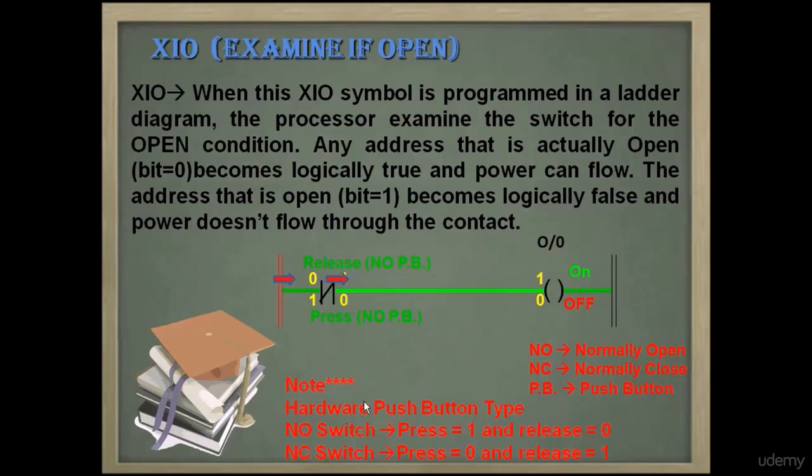There are two types of push buttons. First is NO type or normally open type. If this push button is pressed on hardware, then it sends bit 1, and in reverse condition, it sends bit 0. Second is NC type or normally closed type. If this push button is pressed on hardware, then it sends bit 0, and in reverse condition, it sends bit 1.